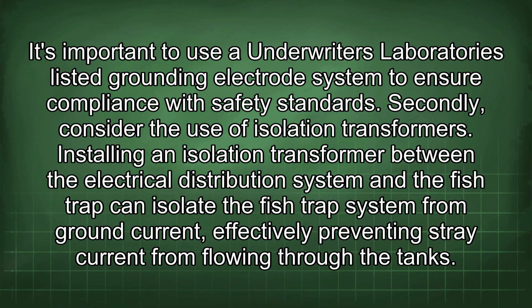Secondly, consider the use of isolation transformers. Installing an isolation transformer between the electrical distribution system and the fish trap can isolate the fish trap system from ground current, effectively preventing stray current from flowing through the tanks.